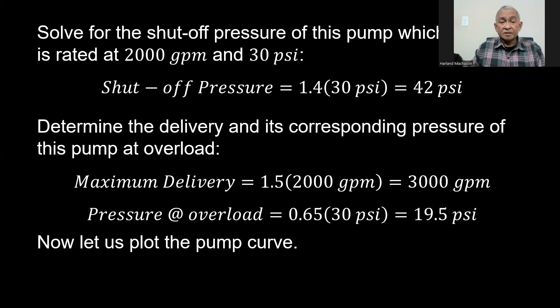We determine the delivery and corresponding pressure of this pump at overload. Maximum delivery is 1.5 times the rated delivery: 1.5 × 2,000 GPM = 3,000 GPM. Pressure at overload is 0.65 times the rated PSI: 0.65 × 30 = 19.5 PSI.